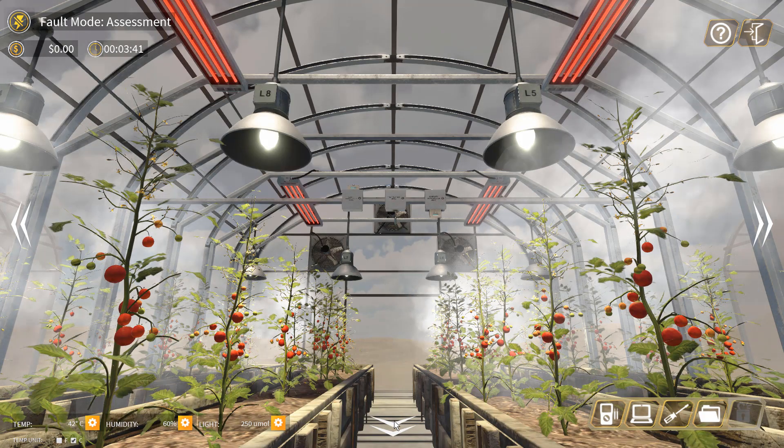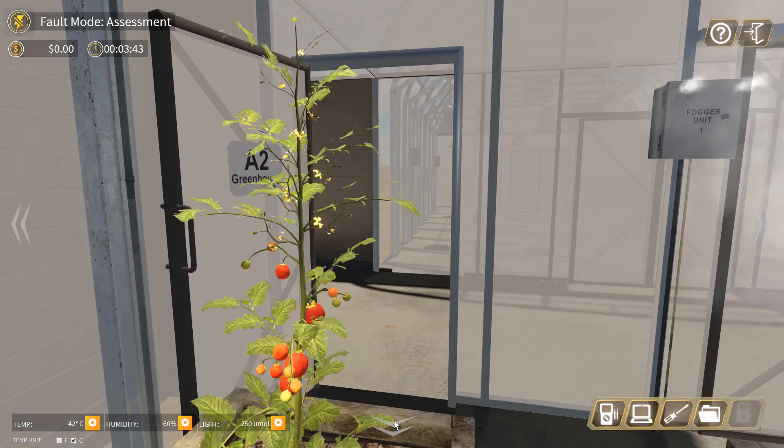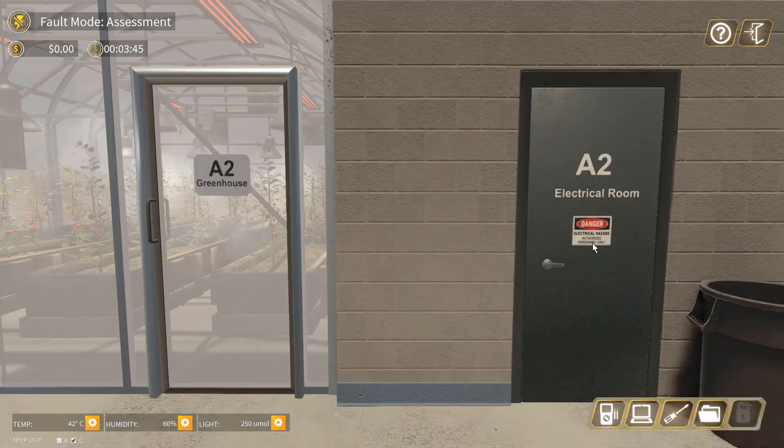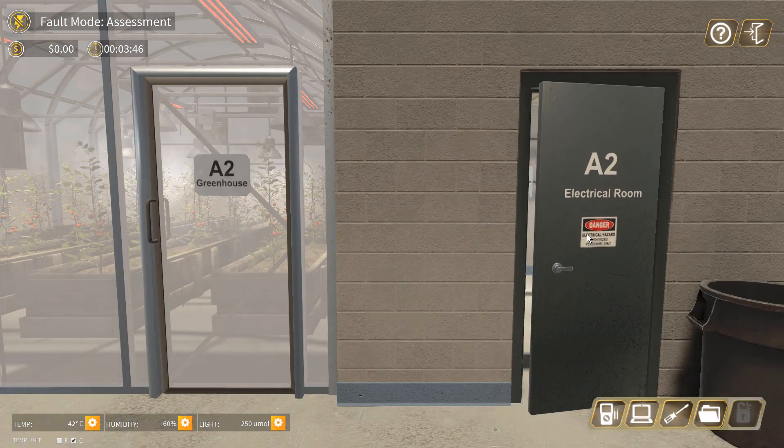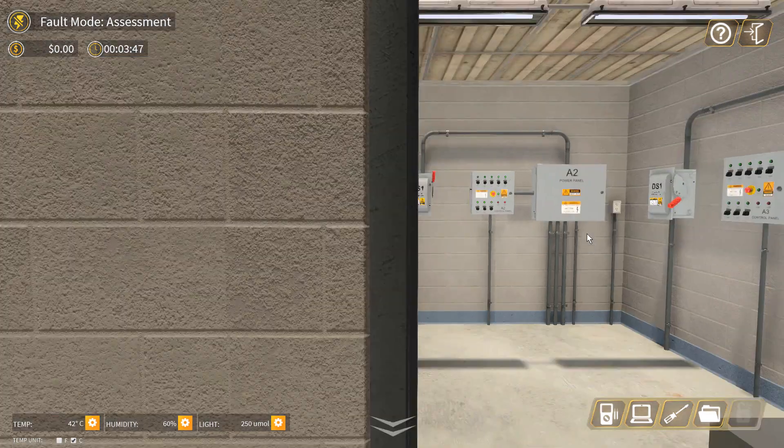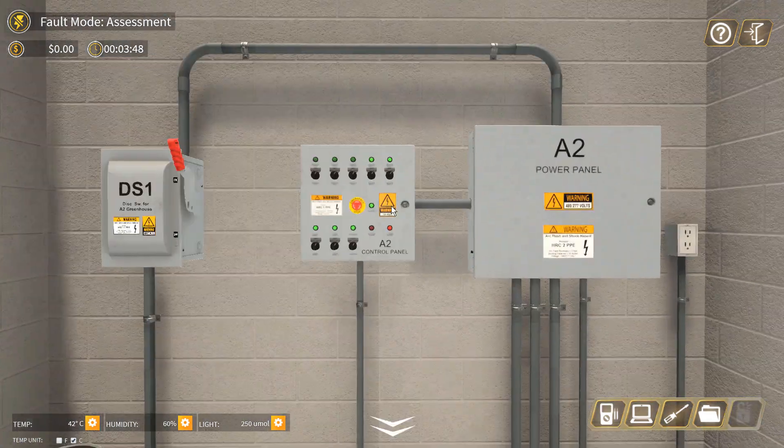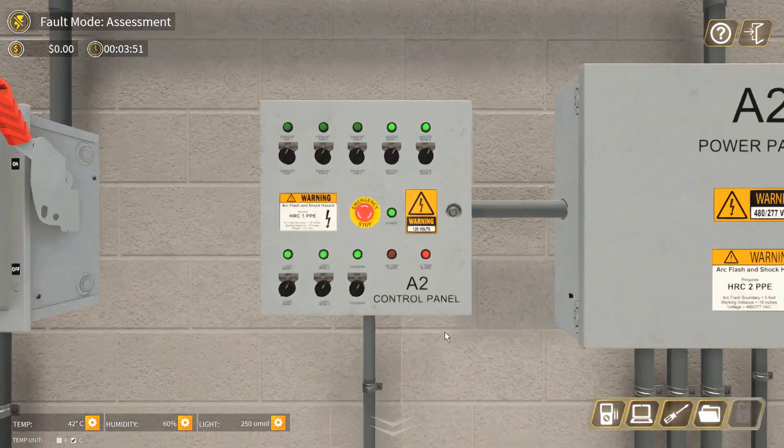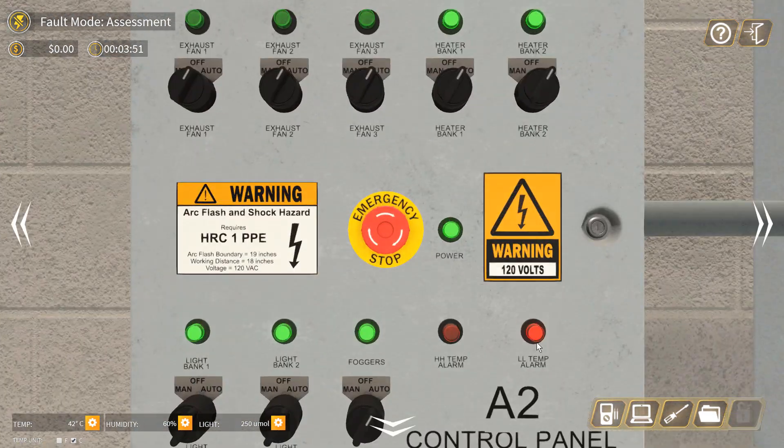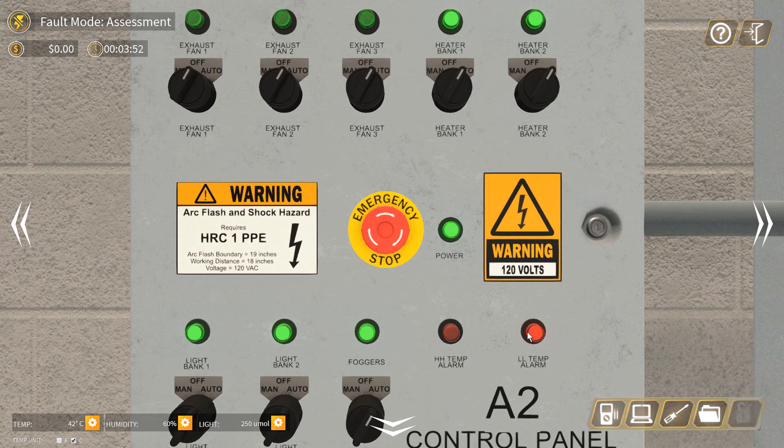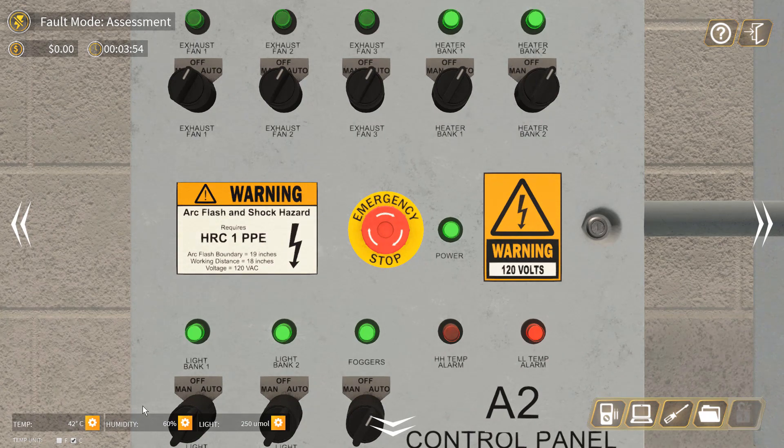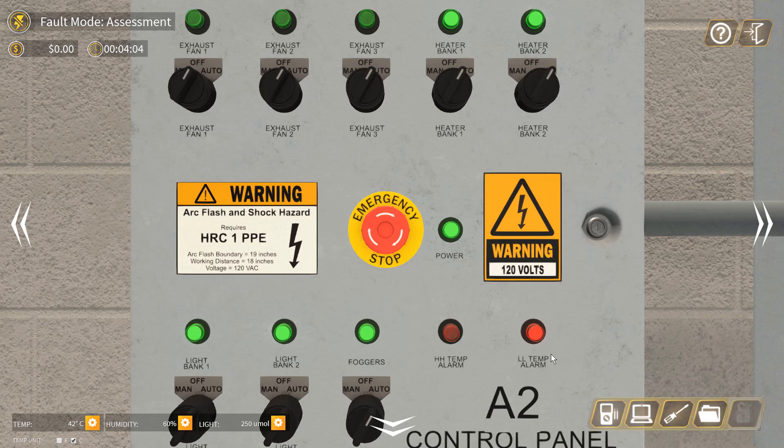Before we do that, let's go to the control room and see what is wrong. As you can see, the low-low temperature alarm happened, which is not true because the current temperature is 42 degrees Celsius. It's supposed to give the high temperature alarm. It detected the wrong temperature - where the temperature is low - so the heater turns on.